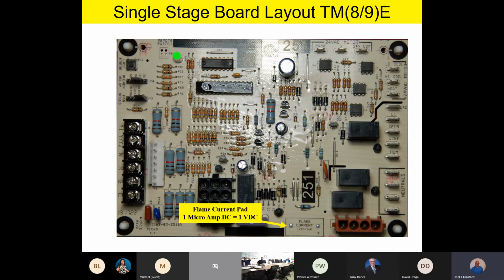Now, if the technician still has a flame current meter, he can still use that if he wants to by unplugging the flame sensor and hooking his meter up appropriately. But this flame current pad, we feature this on all of our Johnson Controls Champion furnaces. It's a really slick feature. Now a technician doesn't have to have a special meter. All they do is take their voltmeter, go to DC volts, and read the voltage on those two little contact points with a DC voltmeter.